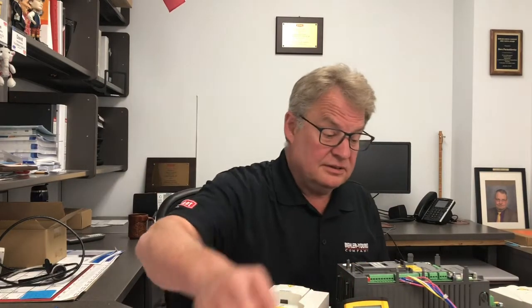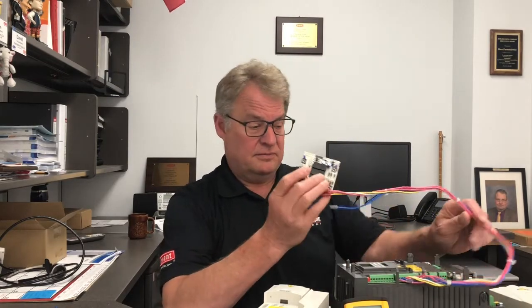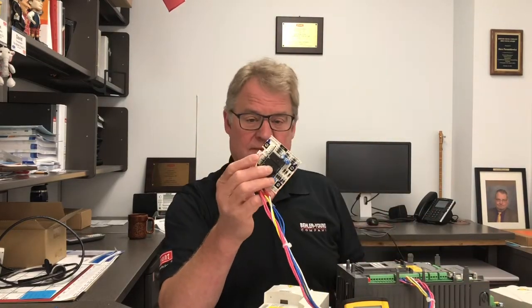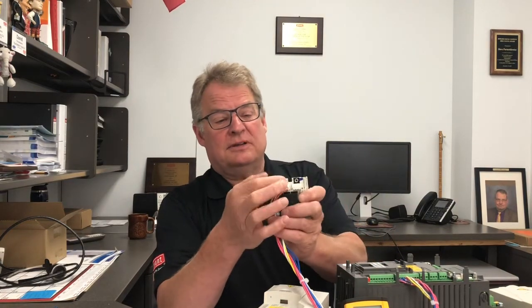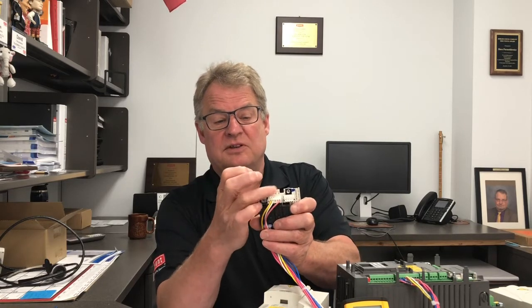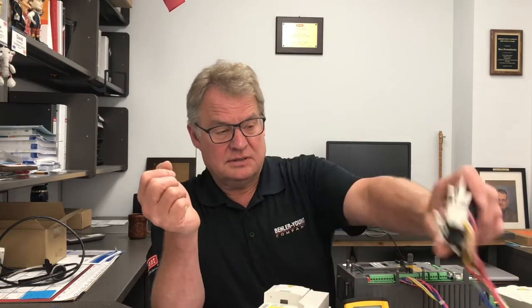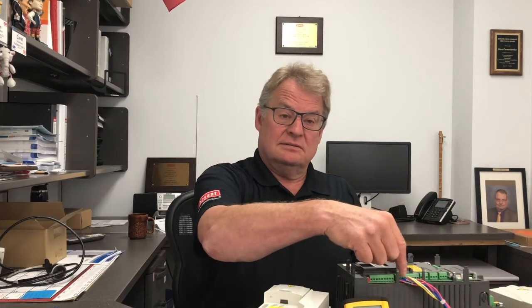Okay, so that's how I check for a signal. So, do I have a relay closure from the relay board when it's being called for by the unit? If not, the relay board is bad. Now I want to point out these 2 jumpers here. You can see our factory cut. If we replace this board, we want to make sure we cut those jumpers, because if we don't, the blower will never shut off.